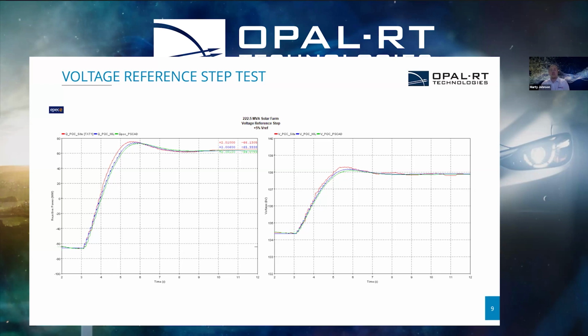The red signal is the site response. This was an actual measured response that we got when we were doing what's called hold point testing, or this compliance testing that we're talking about. You can see that already they match pretty closely. But the blue one is what we got from the hardware in the loop. One thing we can see is that the hardware in the loop response actually better predicts the actual site response than the PSCAD model.